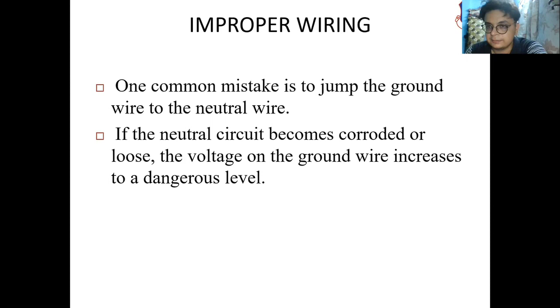This is the main thing that causes electrical damage, that is the jump from the ground wire to the neutral. And if the neutral circuit becomes corroded or loose, the voltage on the ground will increase to a dangerous level. And because of this, dangerous accidents take place.